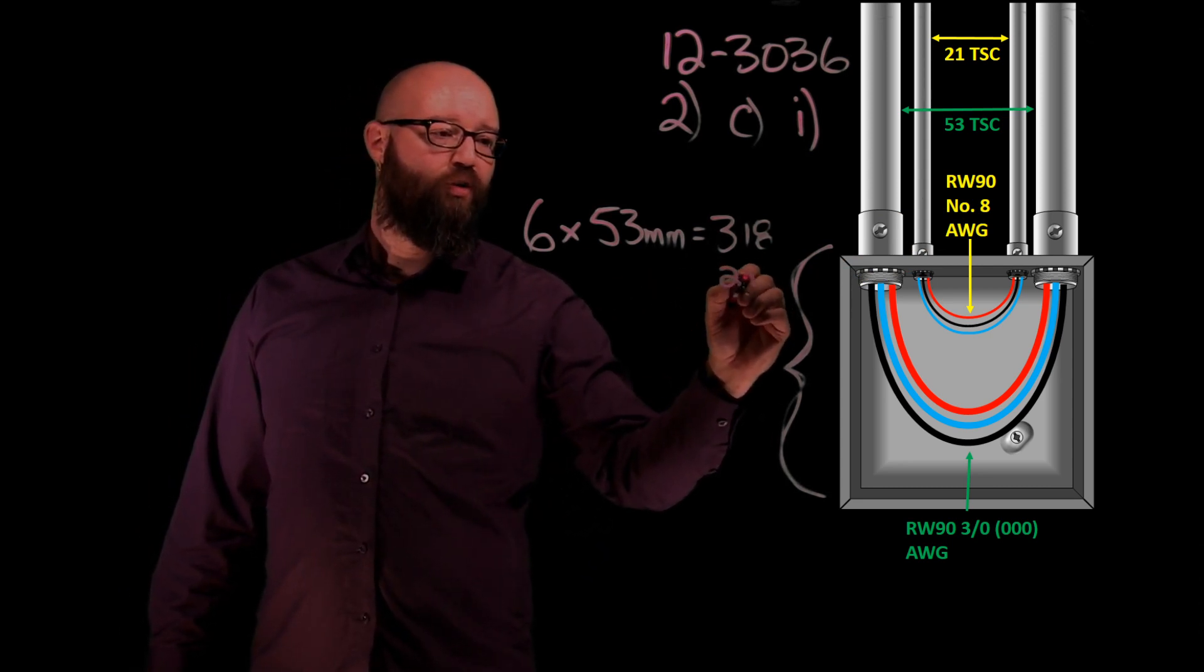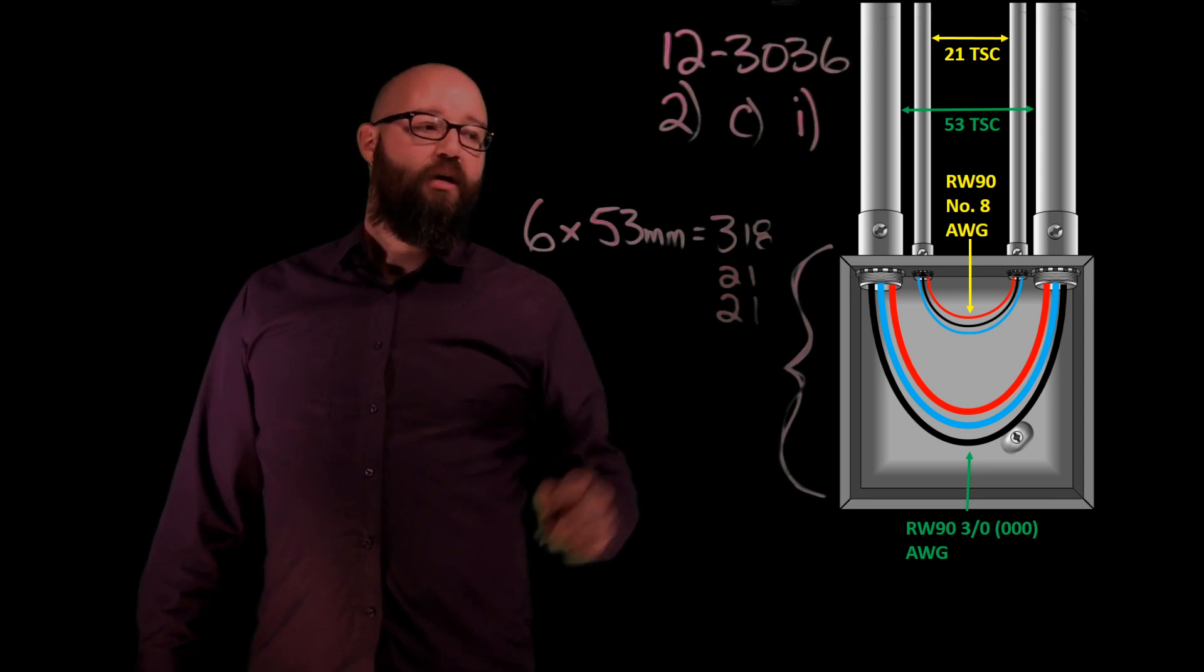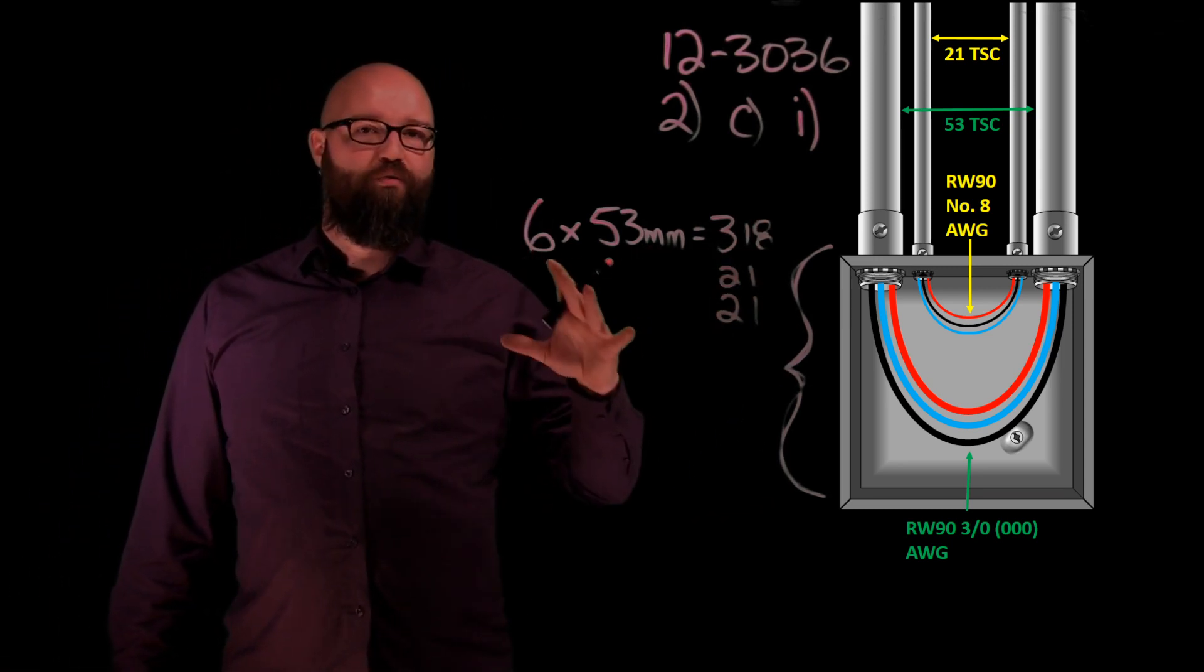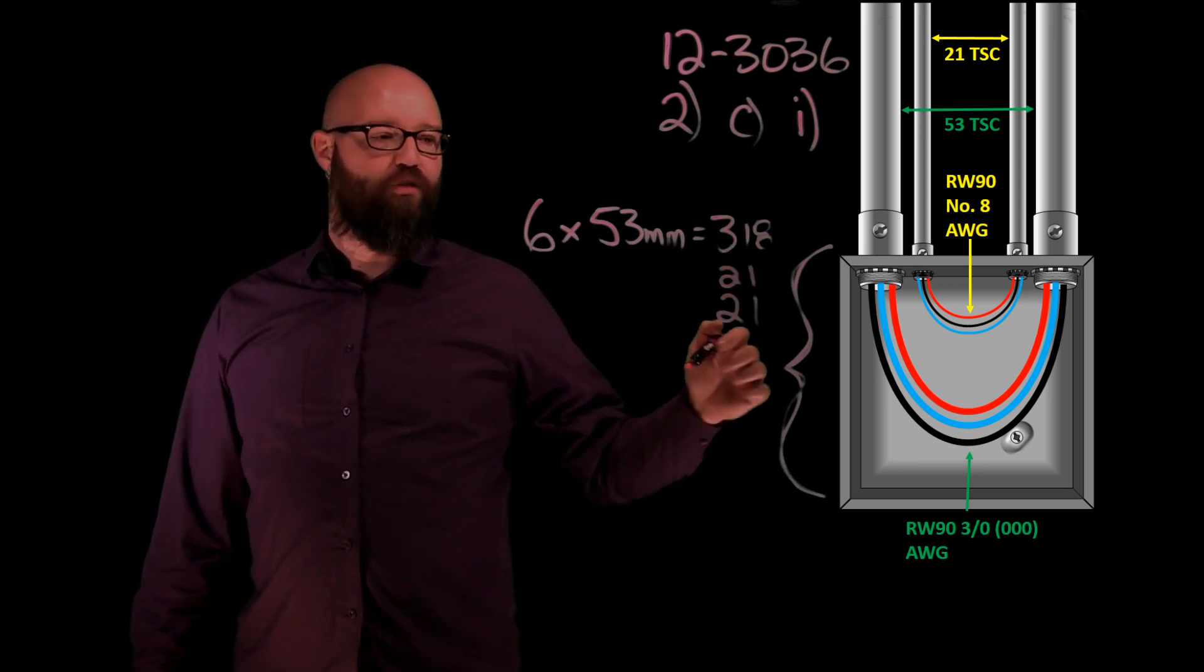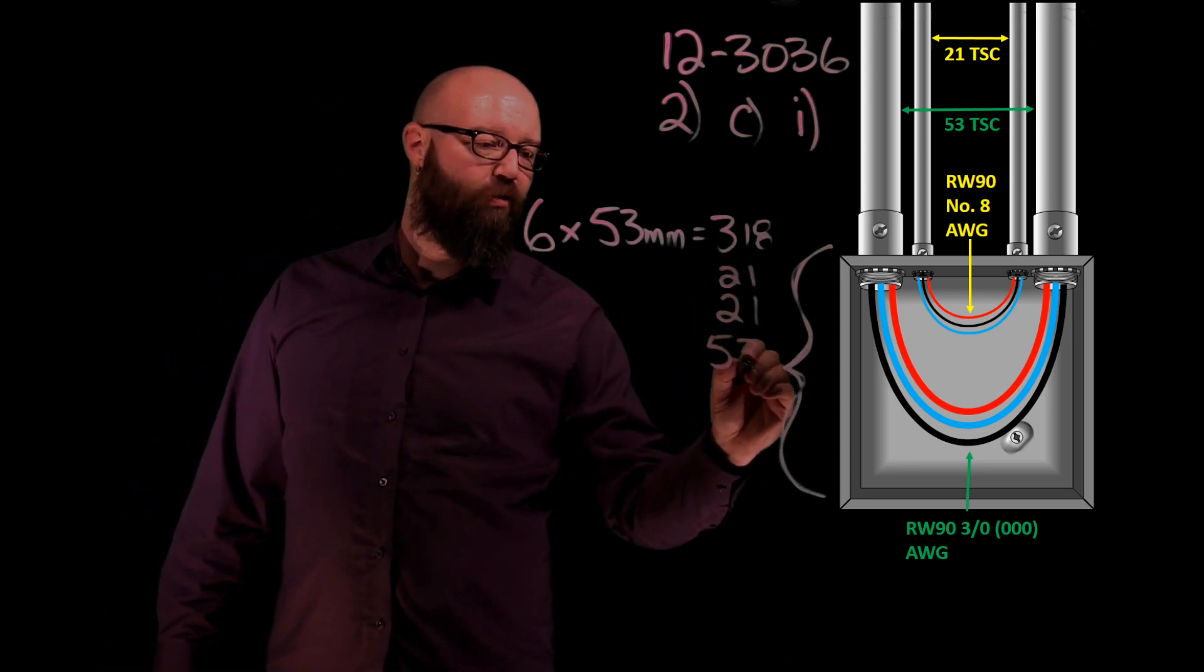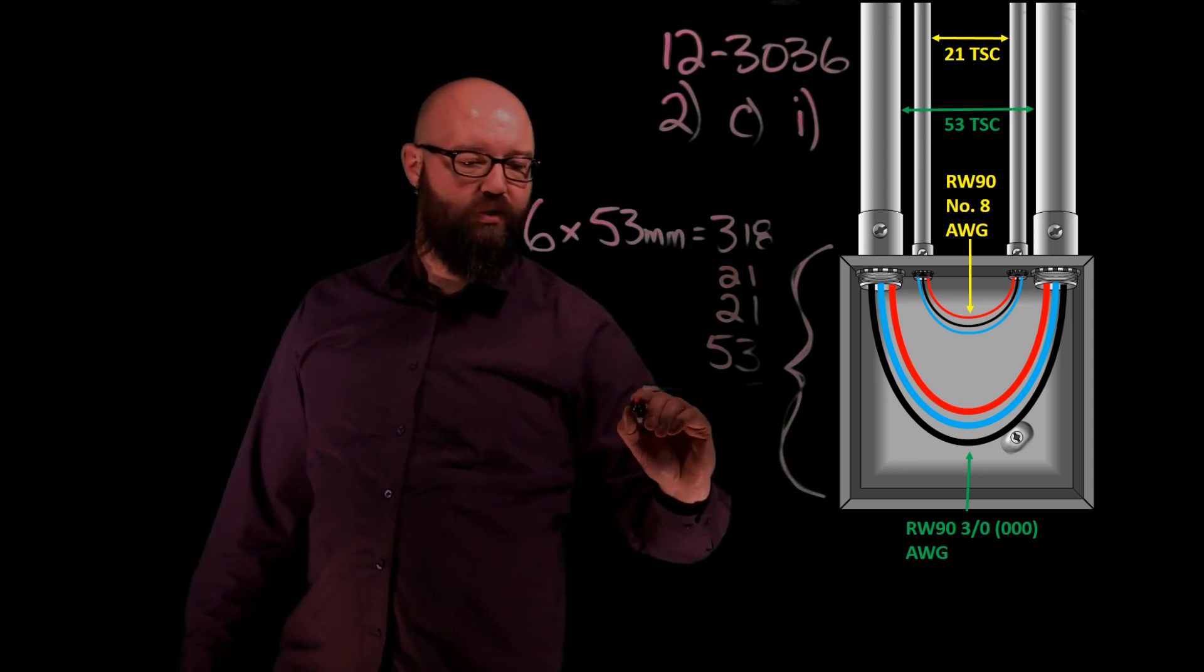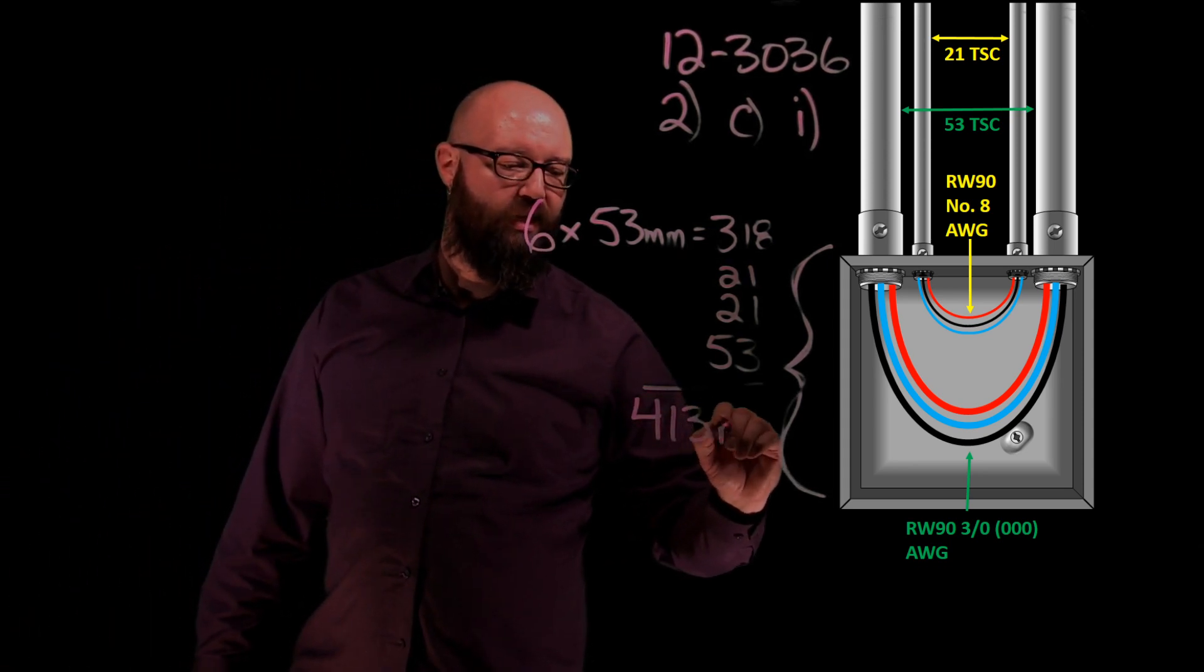So we have our two 21 trade size conduits in there and then we have our other 53 trade size conduits that our three oughts will do that U-turn and make their way into. So we have to add all those in there together. We add those up, we should end up with a total size of 413 millimeters.